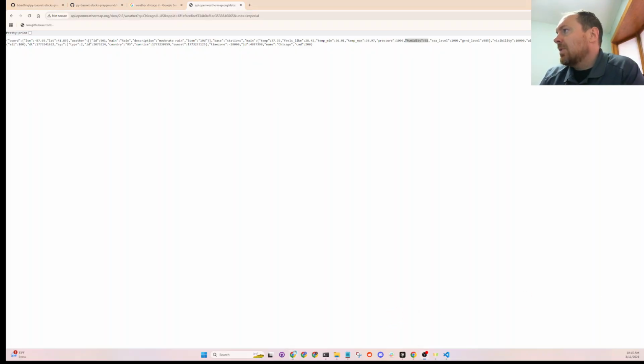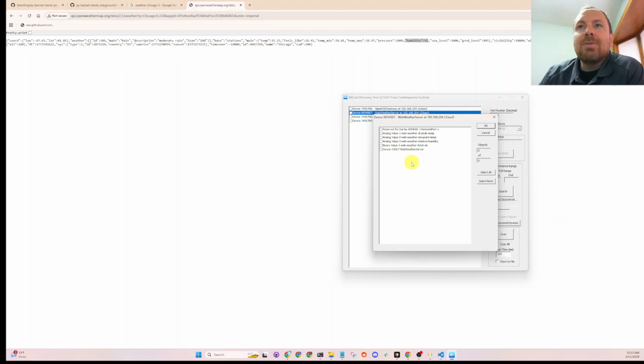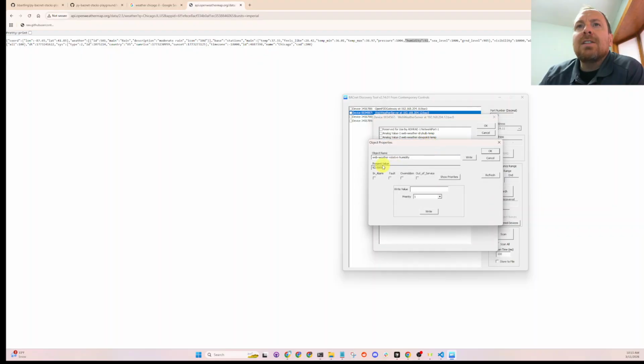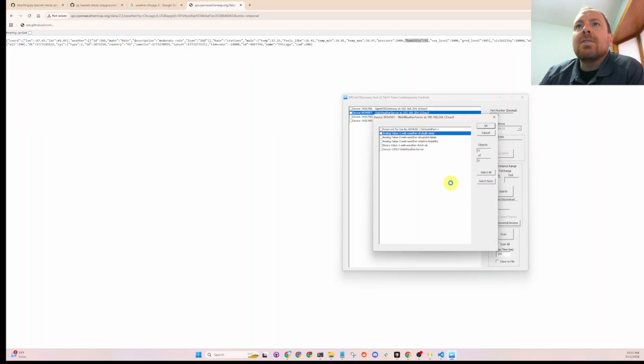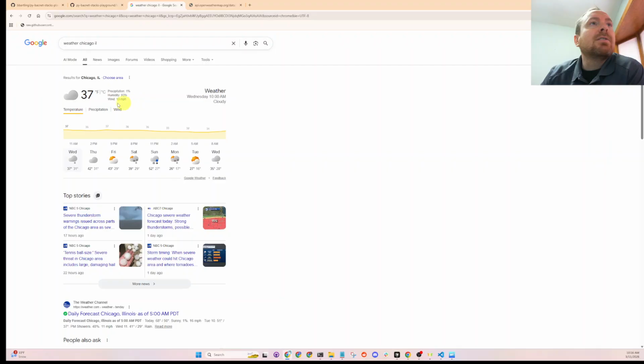So if we go to our BACnet scan tool, like we've done a zillion times on all these YouTube videos, alright, here's our web weather station where we ran it with our correct arguments, if you remember. So our relative humidity should be in the 90s, 92, and our dry bulb temperature 37.33. If you Google weather, that's exactly what you're reading from Google.